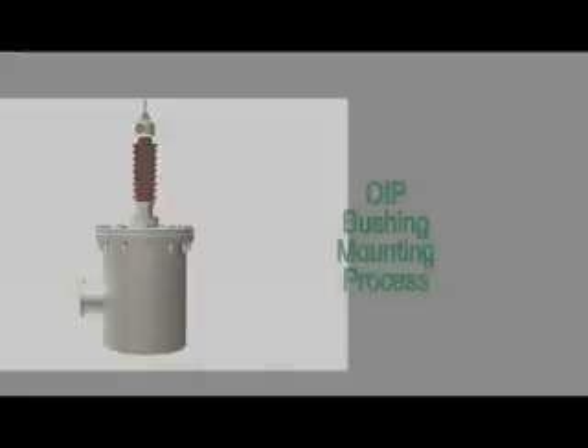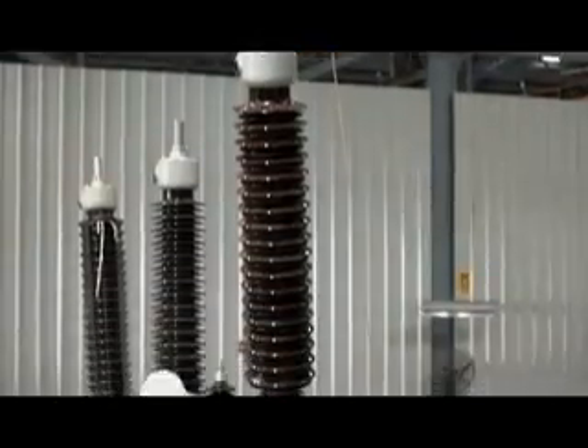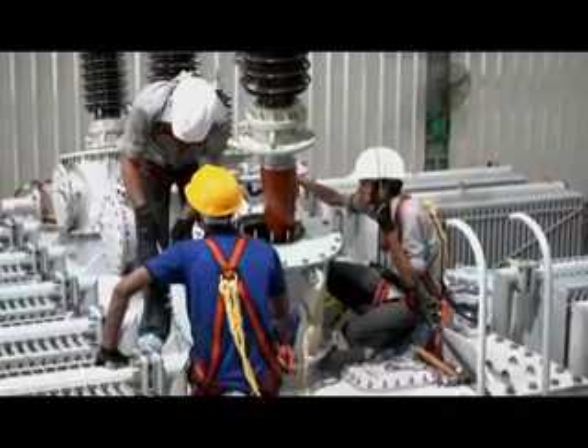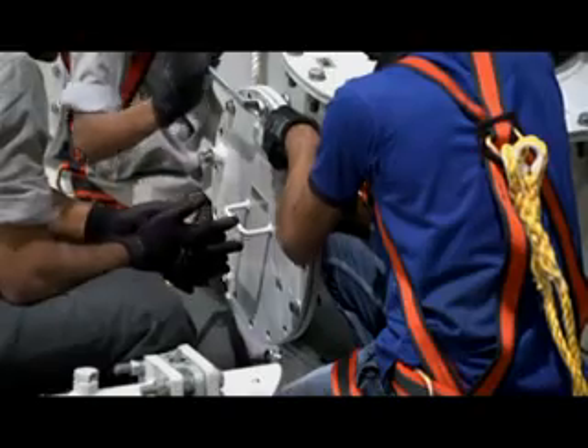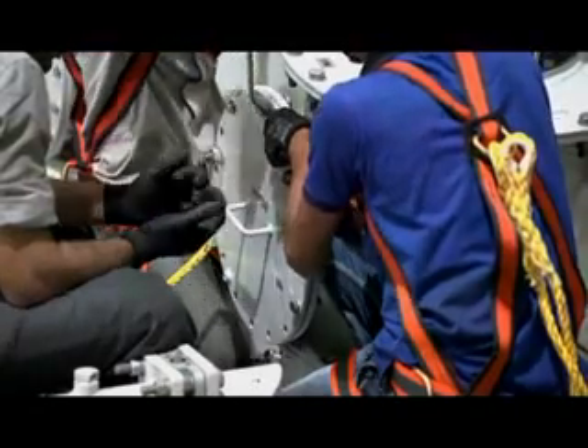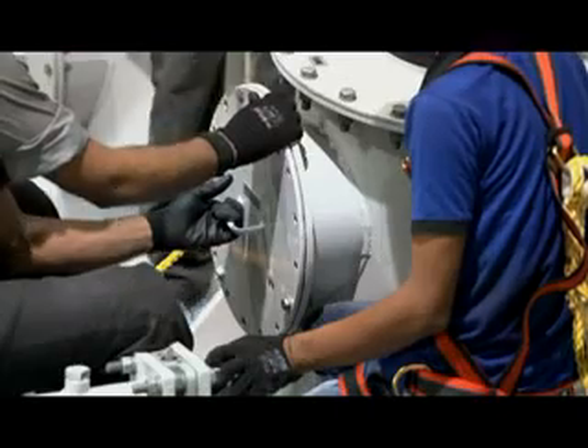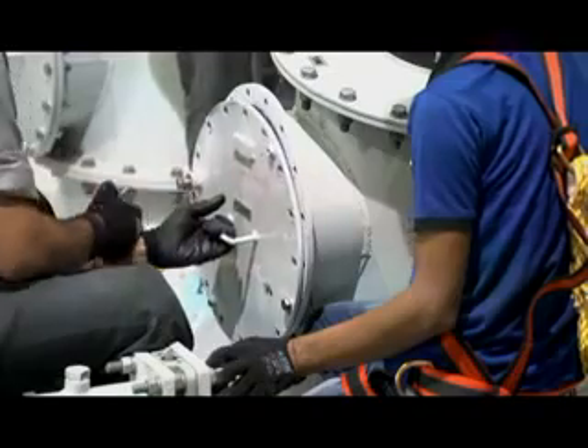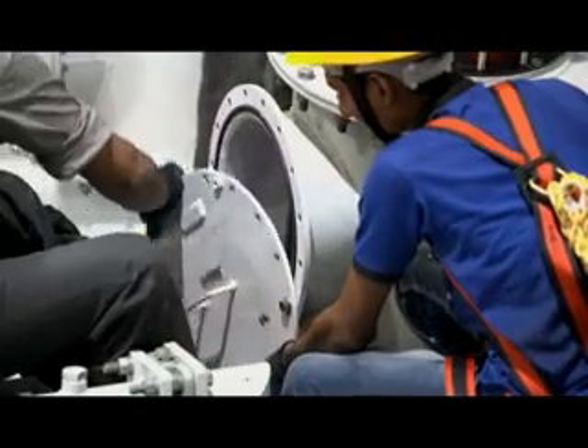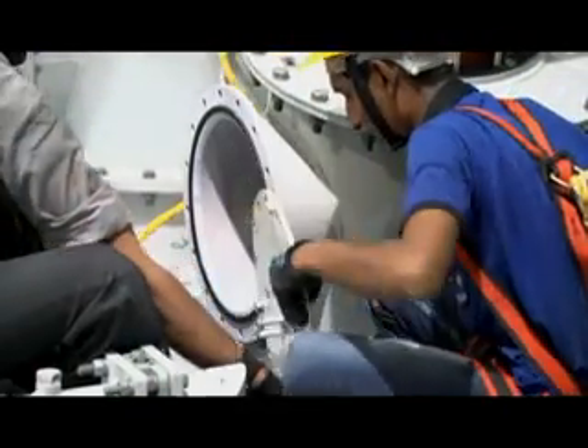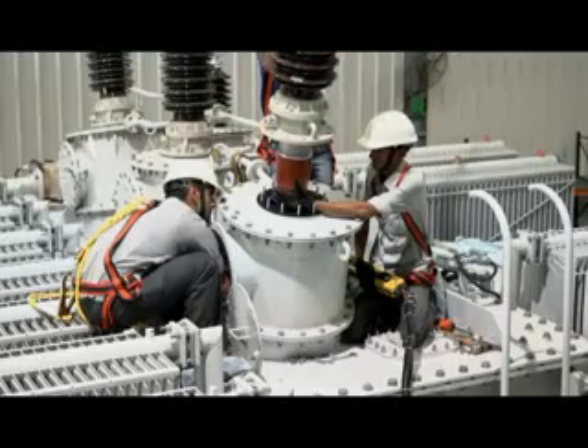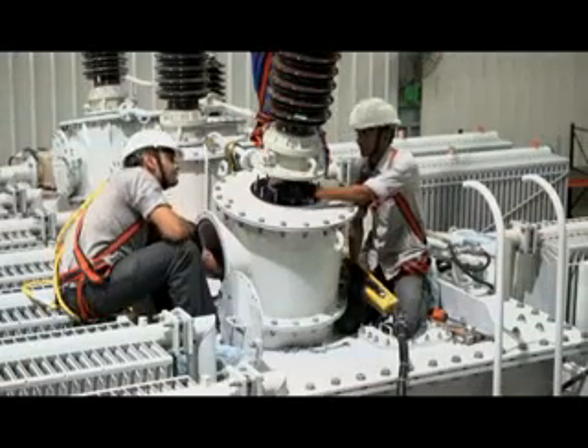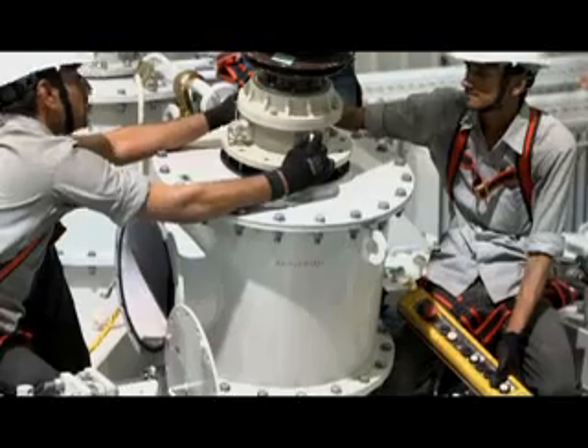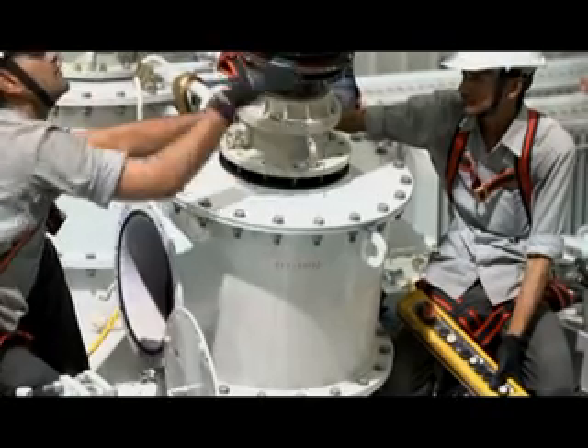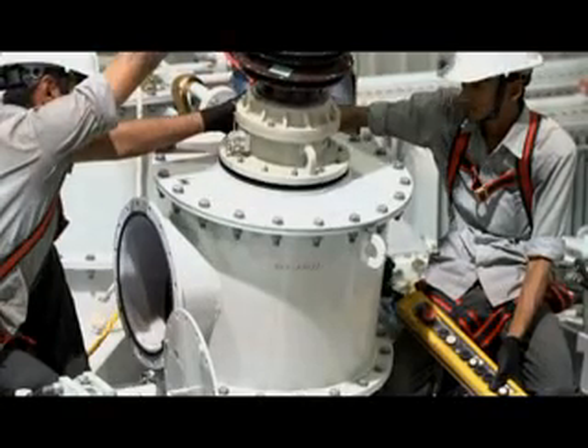OIP bushing fitting. The oil-impregnated paper insulated bushings are used to connect overhead lines to transformers. These are mounted on transformers in a vertical or inclined position at a maximum inclination of 30 degrees from the vertical. The condenser body is enclosed in a weather-resistant housing consisting of a top expansion chamber, an upper porcelain, a welded flange, ground sleeve assembly, a lower porcelain and bottom cap.